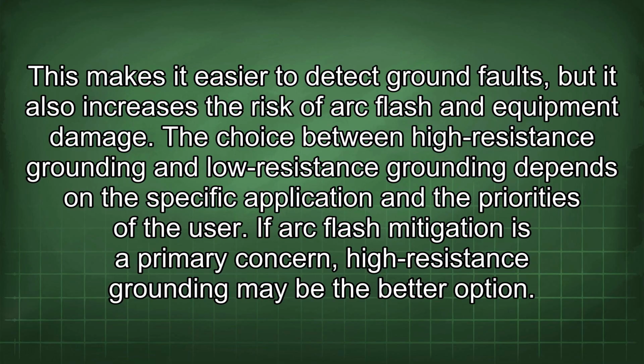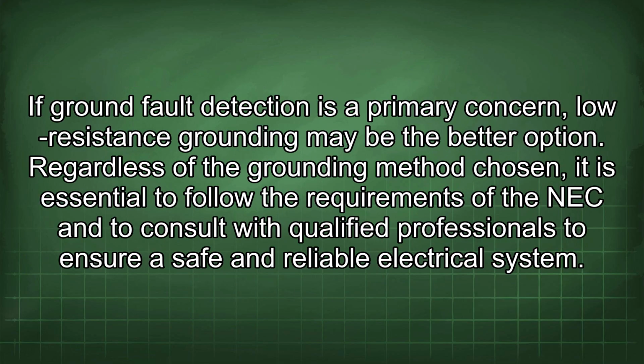The choice between high-resistance grounding and low-resistance grounding depends on the specific application and the priorities of the user. If arc flash mitigation is a primary concern, high-resistance grounding may be the better option. If ground fault detection is a primary concern, low-resistance grounding may be the better option. Regardless of the grounding method chosen, it is essential to follow the requirements of the NEC and to consult with qualified professionals to ensure a safe and reliable electrical system.